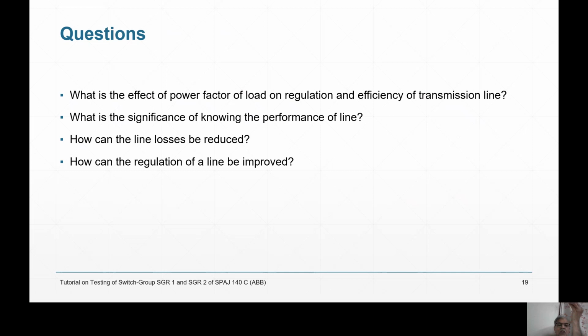The total power that you have to feed at the receiving end is constant. You cannot change it. But the power factor is reduced. If the power factor is reduced and voltage is constant, then current only has to increase. And if current increases, I square R losses will increase. And if I square R losses increase, the efficiency of the transmission line will be bad and the regulation of the transmission line will be bad, right? That will be the effect of power factor. That is the reason why the electricity company insists on a high power factor. They are very particular about power factor.